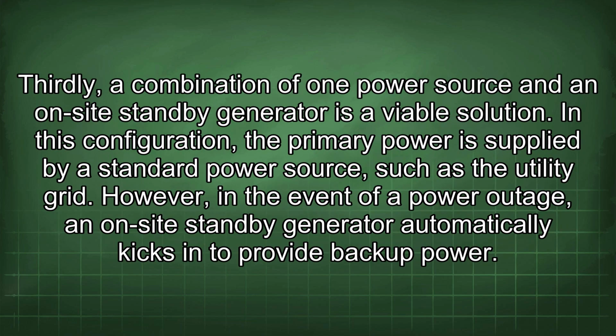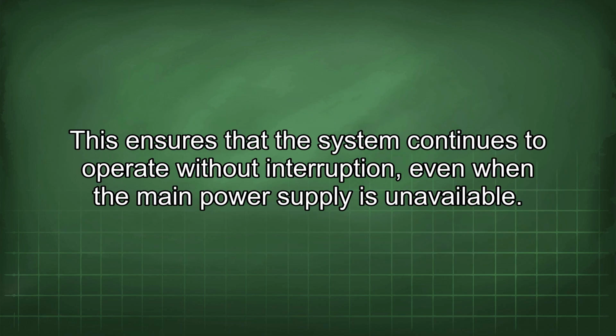Thirdly, a combination of one power source and an on-site standby generator is a viable solution. In this configuration, the primary power is supplied by a standard power source, such as the utility grid. However, in the event of a power outage, an on-site standby generator automatically kicks in to provide backup power. This ensures that the system continues to operate without interruption, even when the main power supply is unavailable.